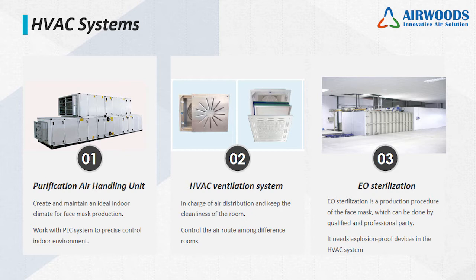Regarding this, we need to have a precise control system for the AHU of the HVAC system. We control the AHU system by using a PLC controller. The PLC can monitor the room temperature, humidity, and pressurization through sensors. We provide and supply the temperature, humidity, and pressure sensors along with the control box. Then the AHU PLC controller can adjust the AHU output automatically according to our settings. We have the settings of the original data of the temperature and the humidity, right?